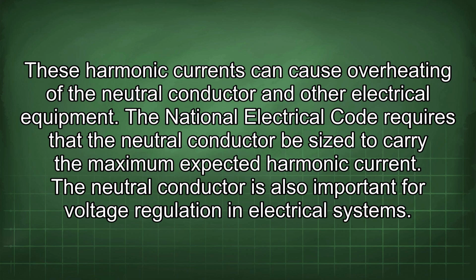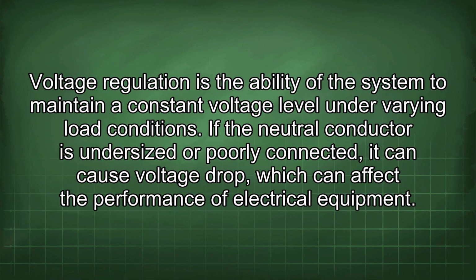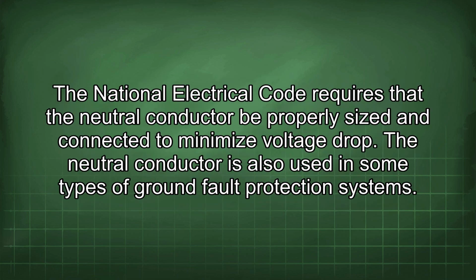The neutral conductor is also important for voltage regulation in electrical systems. Voltage regulation is the ability of the system to maintain a constant voltage level under varying load conditions. If the neutral conductor is undersized or poorly connected, it can cause voltage drop, which can affect the performance of electrical equipment. The National Electrical Code requires that the neutral conductor be properly sized and connected to minimize voltage drop.